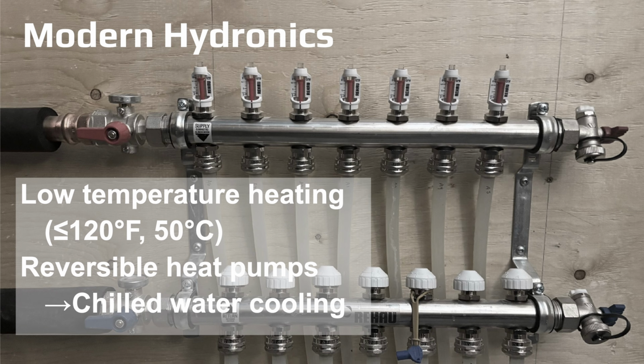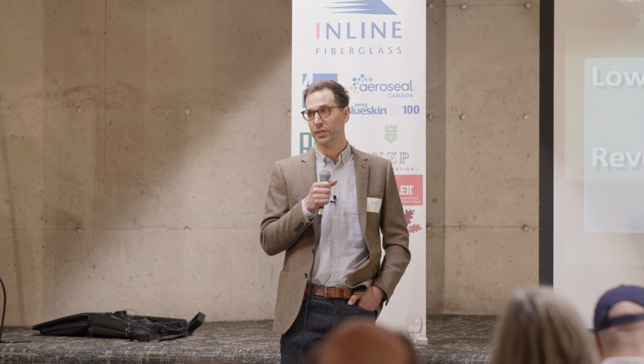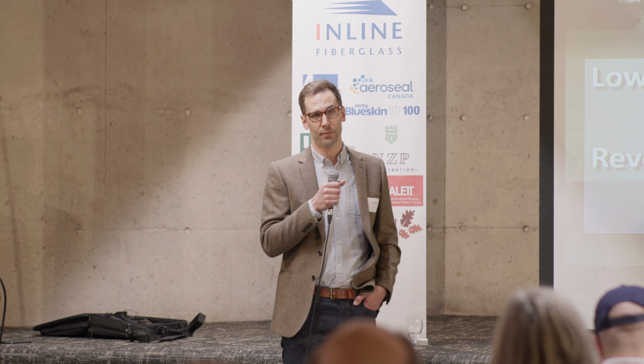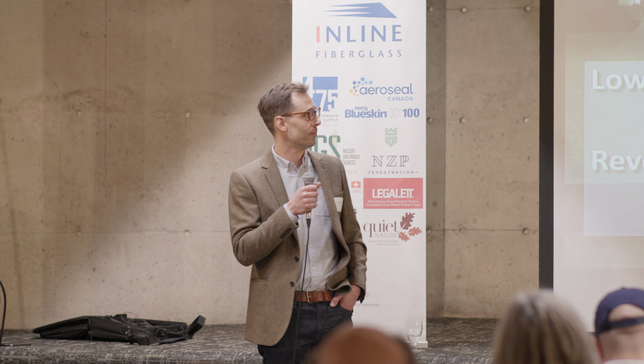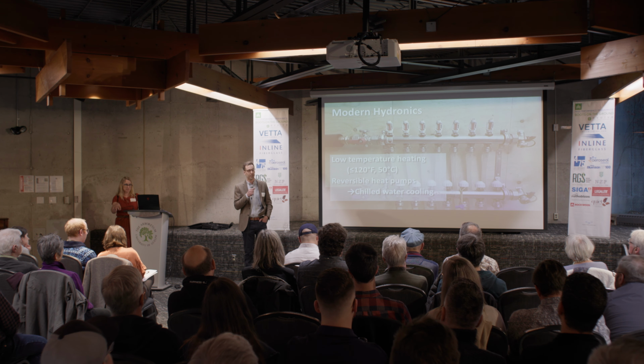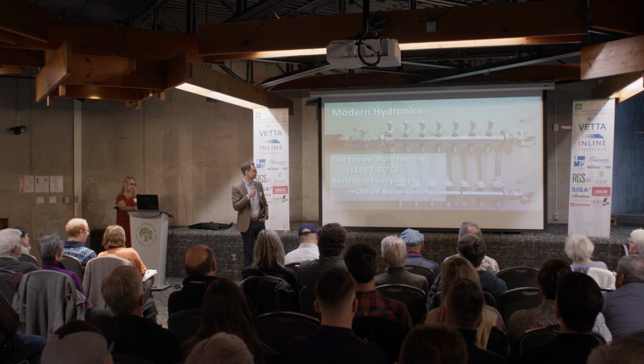There are some high temperature heat pumps coming to market to address that, but on day one with a really good building enclosure, there's no reason we should be designing hydronic systems to operate at any more than 120 degrees Fahrenheit on the coldest day of the year. And we can actually go colder than that.